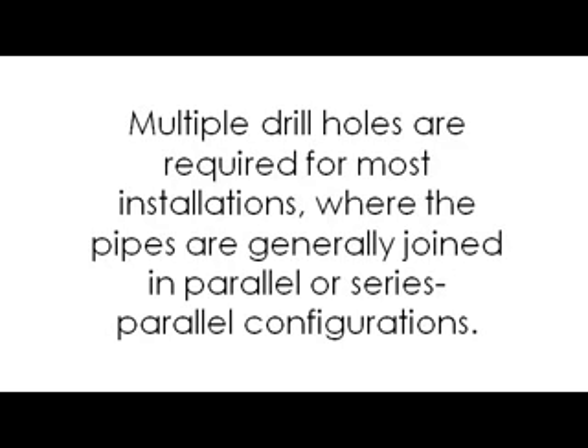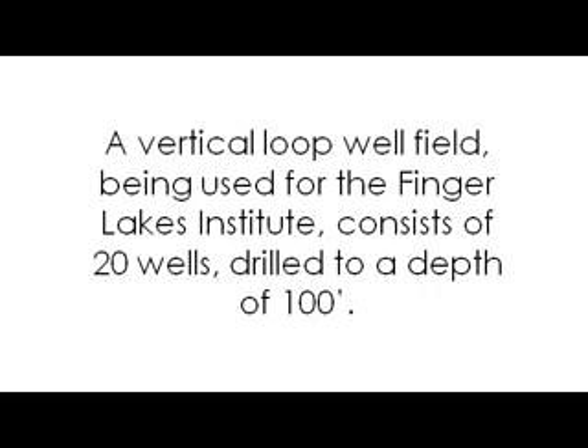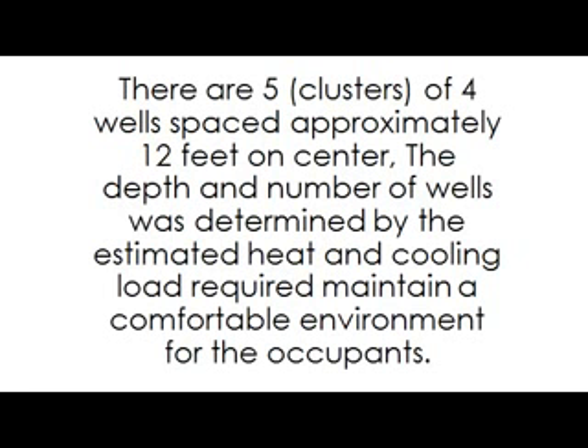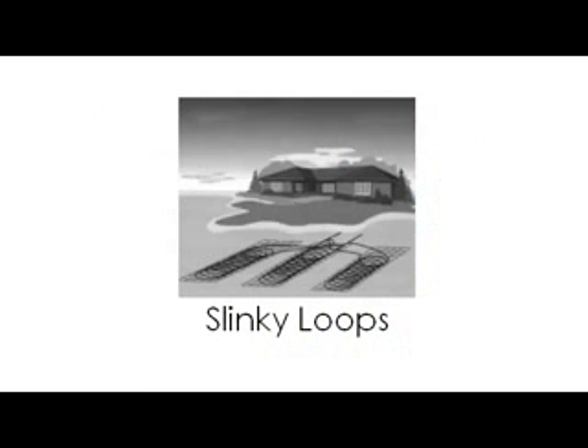A vertical loop well field, being used for the Finger Lakes Institute, consists of 20 wells drilled to a depth of 100 feet. There are 5 clusters of 4 wells spaced approximately 12 feet on center. The depth and number of wells was determined by the estimated heat and cooling load required to maintain a comfortable environment for the occupants. Slinky loops.